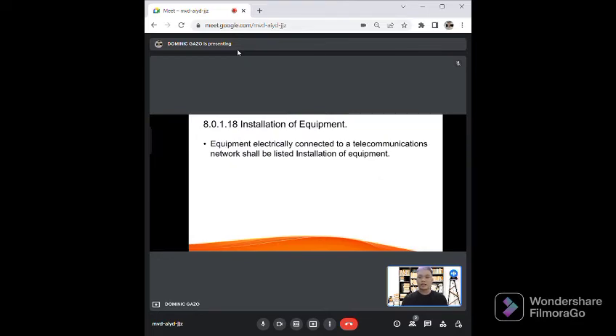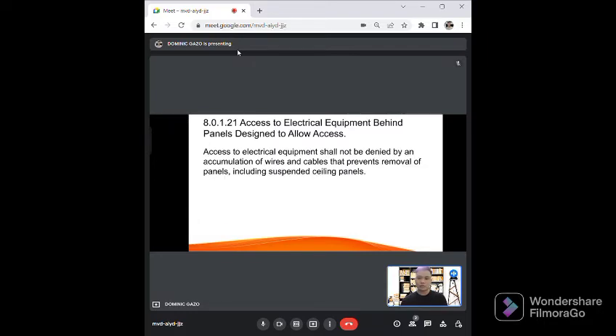For Article 8.0.1.18, installation of equipment, equipment that is electrically connected to a telecommunications network shall be listed in installation equipment. For 8.0.1.21, access to electrical equipment behind panels designed to allow access, access to electrical equipment shall not be denied by an accumulation of wires and cables that prevents removal of panels, including suspended ceiling panels.